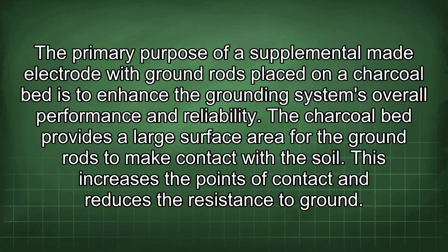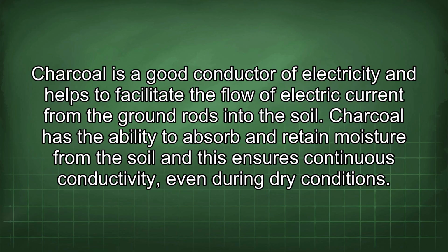The primary purpose of a supplemental made electrode with ground rods placed on a charcoal bed is to enhance the grounding system's overall performance and reliability. The charcoal bed provides a large surface area for the ground rods to make contact with the soil. This increases the points of contact and reduces the resistance to ground. Charcoal is a good conductor of electricity and helps to facilitate the flow of electric current from the ground rods into the soil.